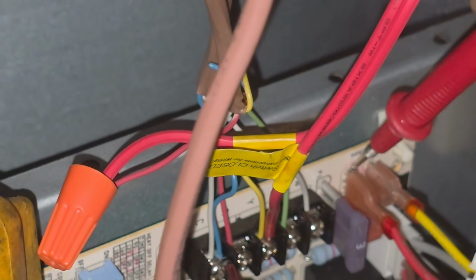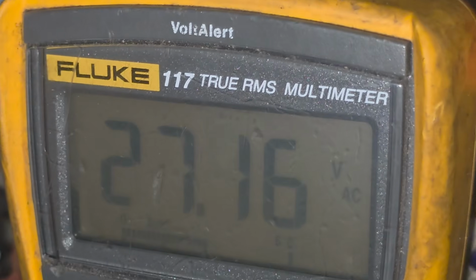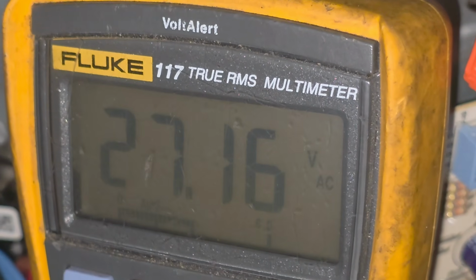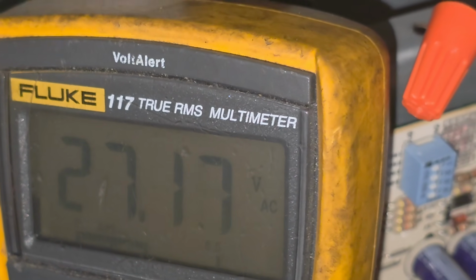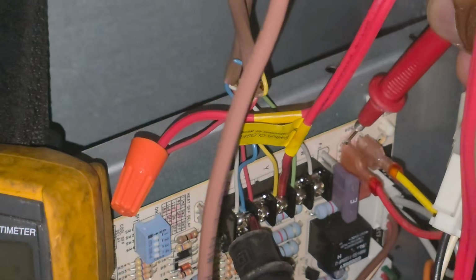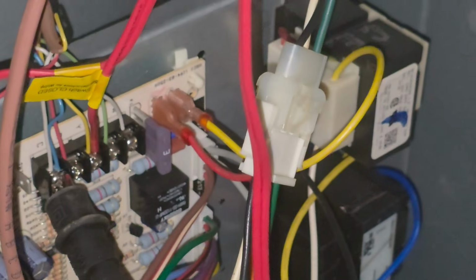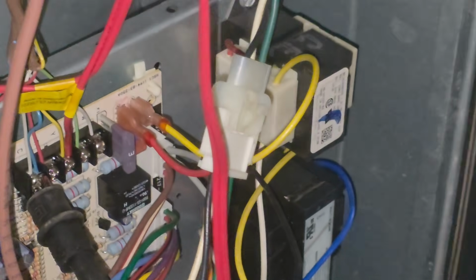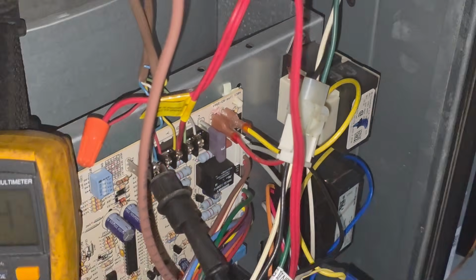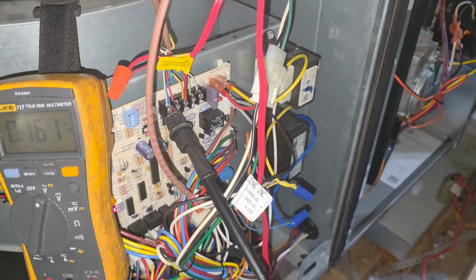Let's go to that terminal right there. You see that? On top of that terminal right there, I'm getting 24 volts. All right, that's what we want right there. If I was getting 0, we wouldn't be getting 24 volts to our board. All right.